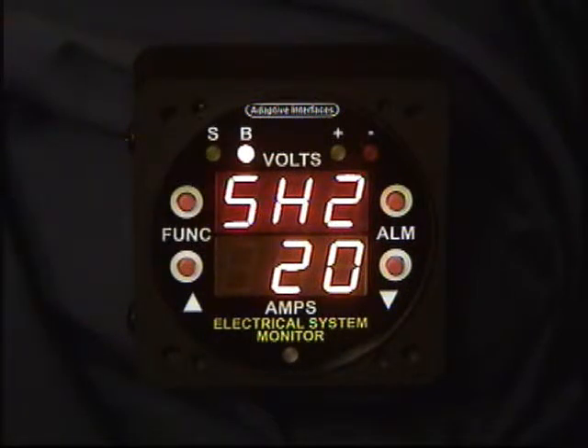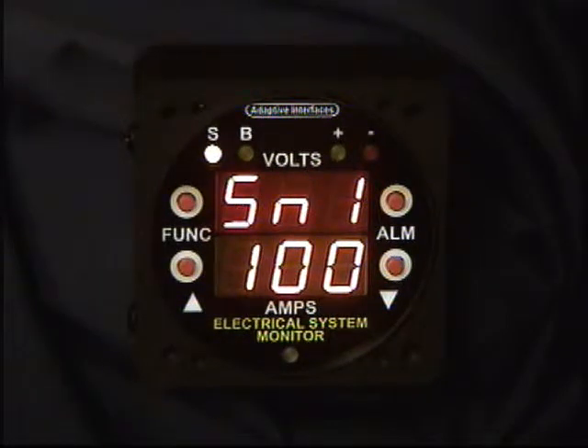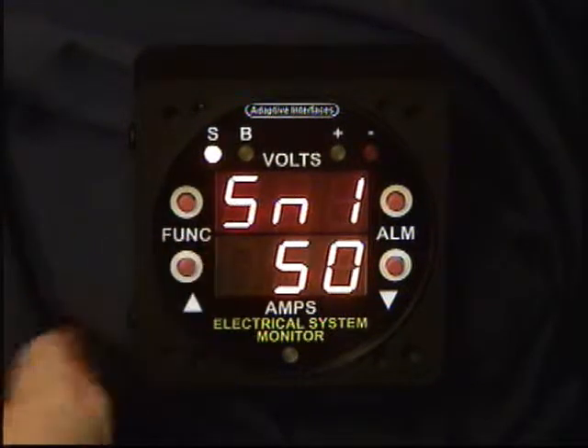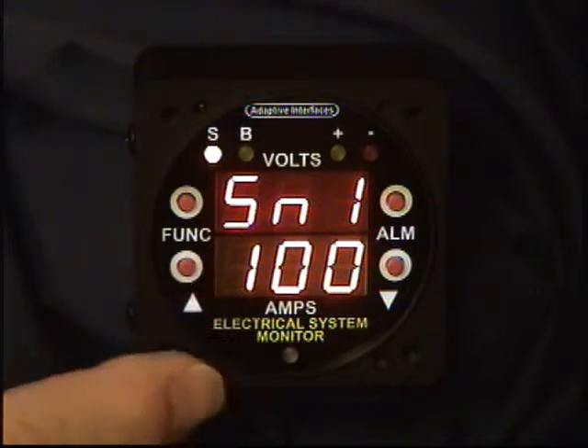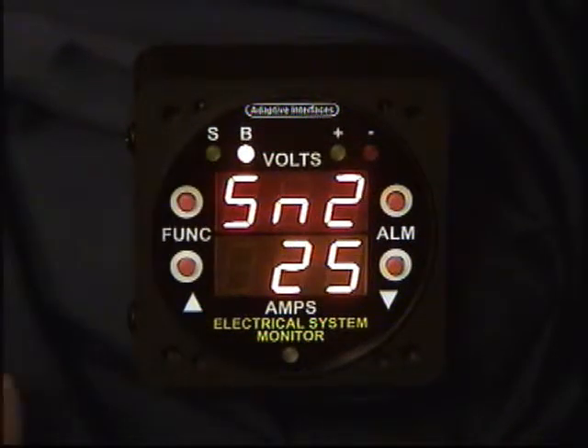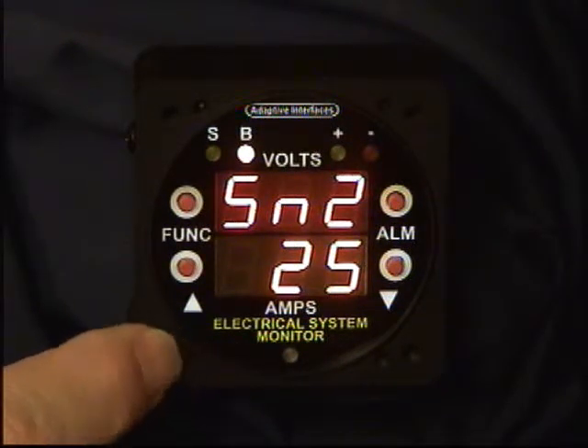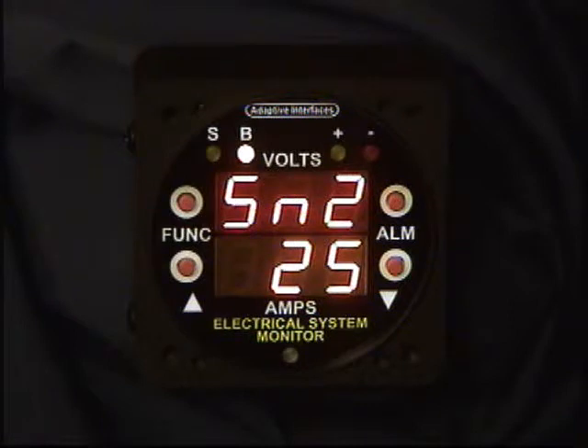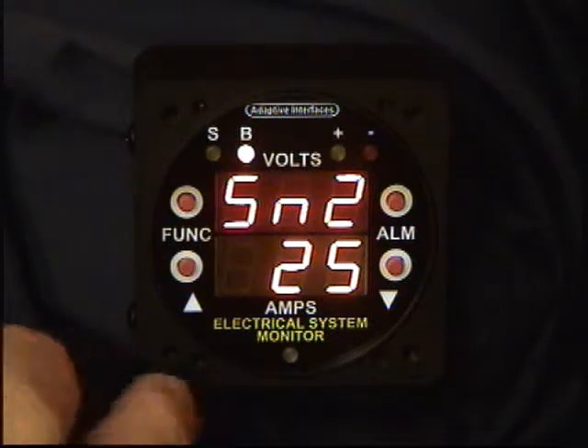Next function is the selection of a shunt for the battery if we're using a shunt. Right now it's set for a 20 amp shunt. We'll go ahead and keep it there. Next function is the type of Hall effect sensor used if the instrument's being used with a Hall effect sensor. We have a selection of either a 100 amp sensor, a 25 amp sensor, or a 50 amp sensor. We'll just go ahead and keep it as a 100 amp sensor. Go on to the next function. A 25 amp Hall effect sensor has been selected for use with the battery. Again, the instrument can be switched to either using a Hall effect sensor or a shunt, and the menu simply allows you to select what type of sensor or what type of shunt you're going to be using, if you're using that particular type.